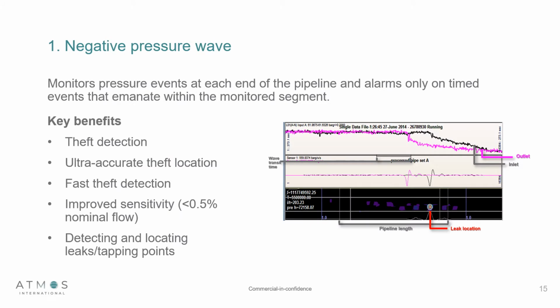The negative pressure wave, as I stated before, monitors pressure events at each end of the pipeline and alarms on timed events that come from a monitored section. And as I stated in the previous slide, the advantages that this has is it's very good for theft detection. It can provide very accurate location, which is critical in pinpointing a leak or a theft point, especially when we're talking about theft, because the thieves will try and hide their activity. It has very good sensitivity, generally less than 1%, and in some cases less than 0.5%.